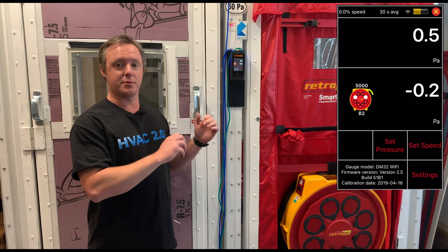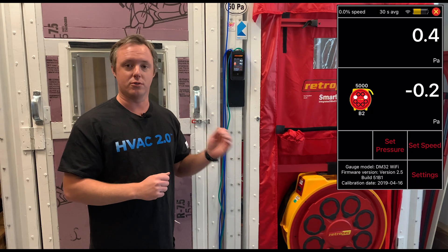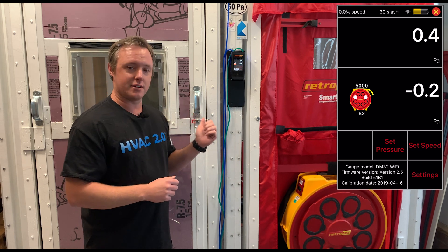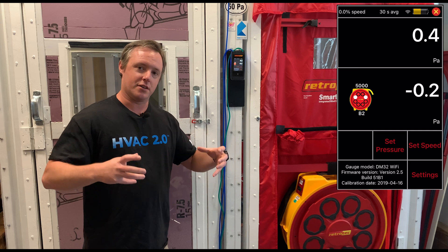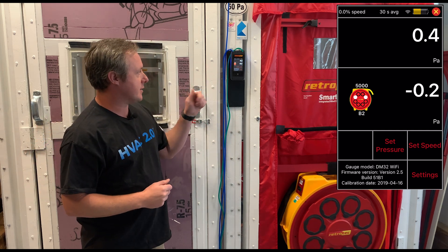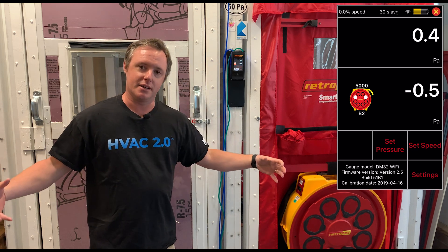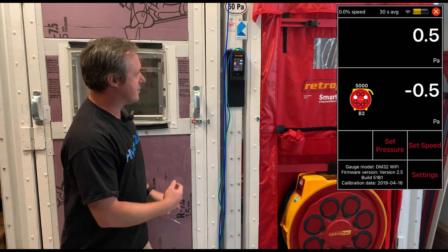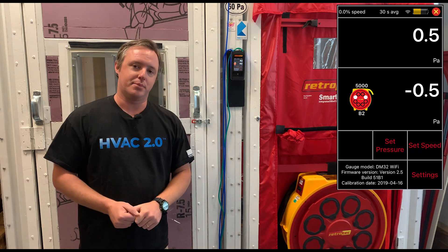What we're doing here is simulating a building during the winter or in a colder climate. As we're heating up that interior air, that more buoyant warmer air is moving upward creating a positive pressure that we can see on channel A, and it's pulling in cooler outdoor air at the bottom creating that negative pressure we see on channel B.